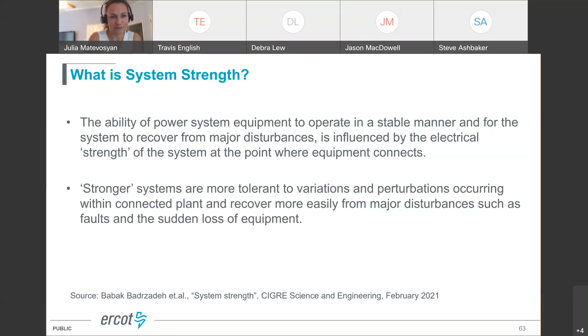You've probably seen that traditionally short circuit ratio is used to characterize system strength. This is mainly because if you do a short circuit calculation at a given point, it gives you a good idea about how far this interconnection point is from contributors of short circuit current, and that is a good characterization of electrical distance between the short circuit current source and the interconnection point that you're studying. And so that's why traditionally short circuit ratio has been used to characterize system strength. Again, the short circuit ratio is a ratio between the short circuit contribution at the interconnection point you're looking at and the capacity of the inverter-based resource that you are trying to connect there. I'll have more about this on the next slide. Next slide, please.